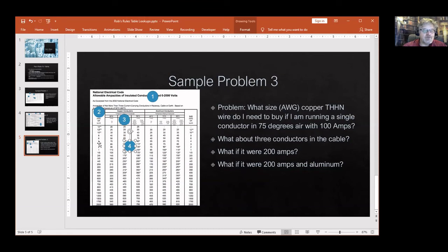In this case it is 100 amps is in the same row as number three AWG so I need a three wire size which is a big wire. All right that's the answer, number three.